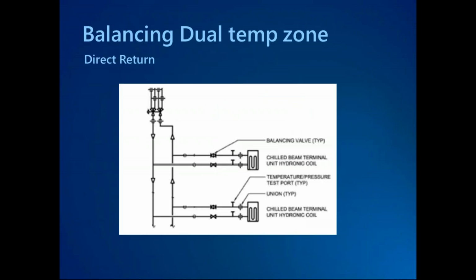So up until now, everything we talked about was the components between the mains, the hot and cold main, and the 6-way itself. I want to take a quick second to mention the balancing and valving required after the 6-way control valve, because you do have all of these components that are getting zoned together. I'm sorry, all of these chilled beams that are getting zoned together somehow. The first is with direct return piping.